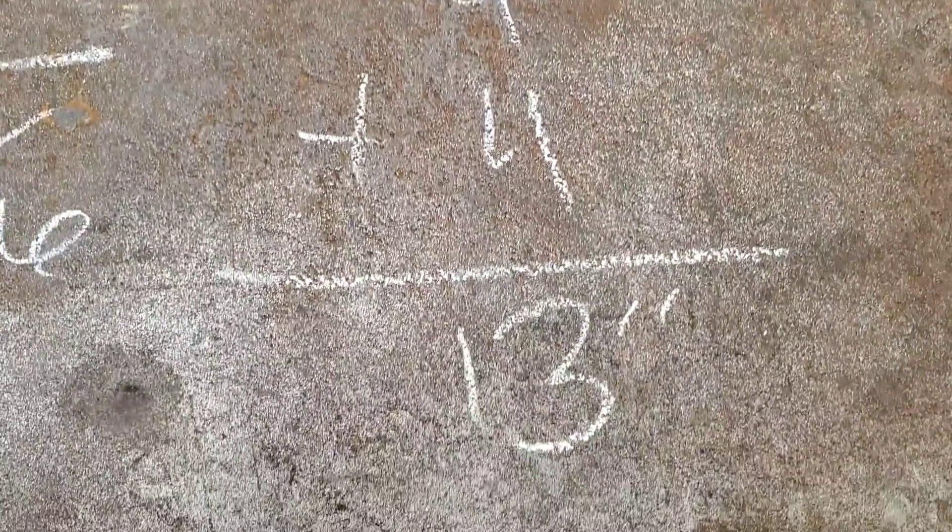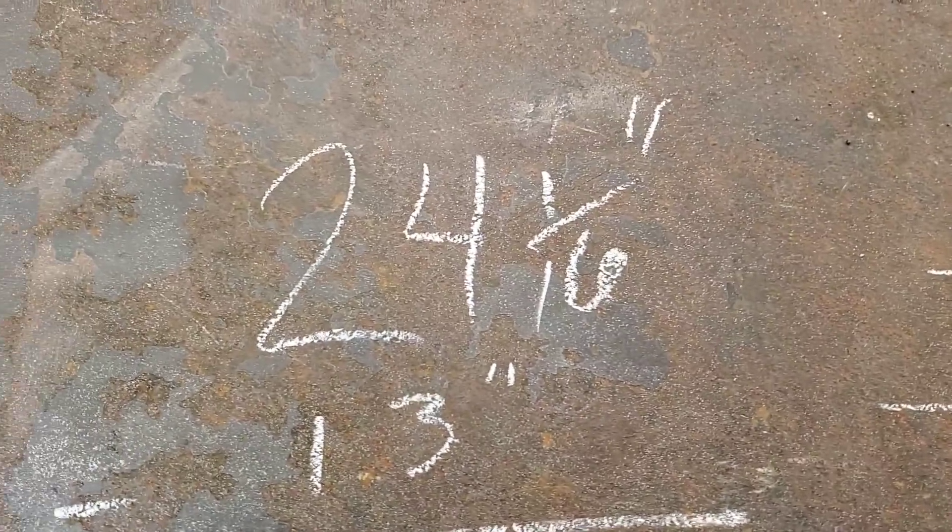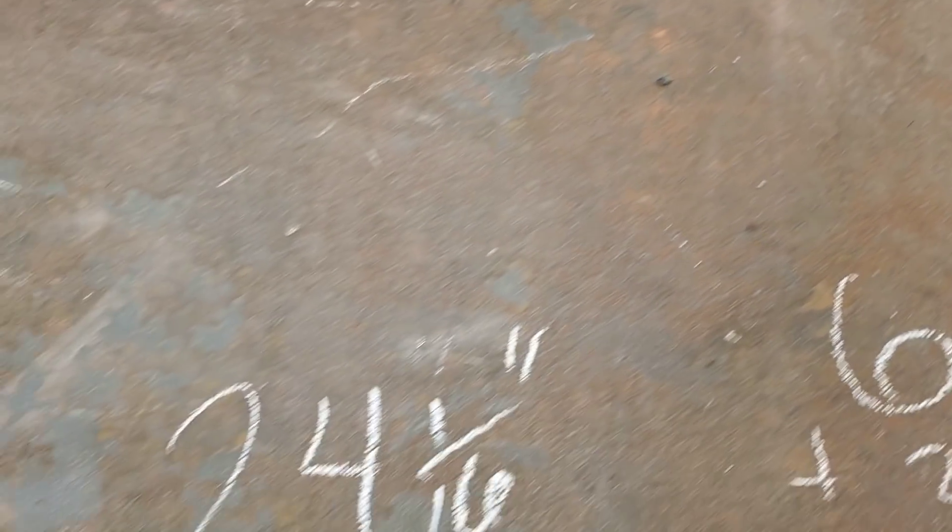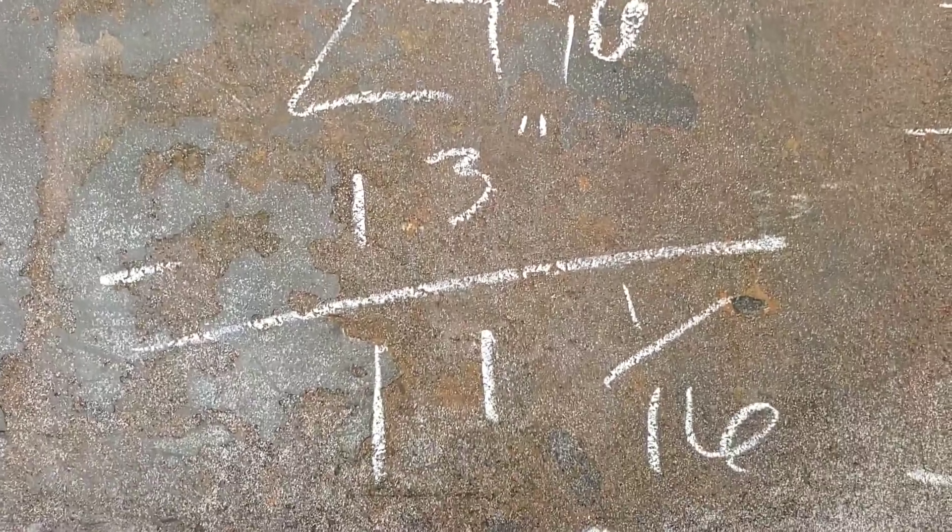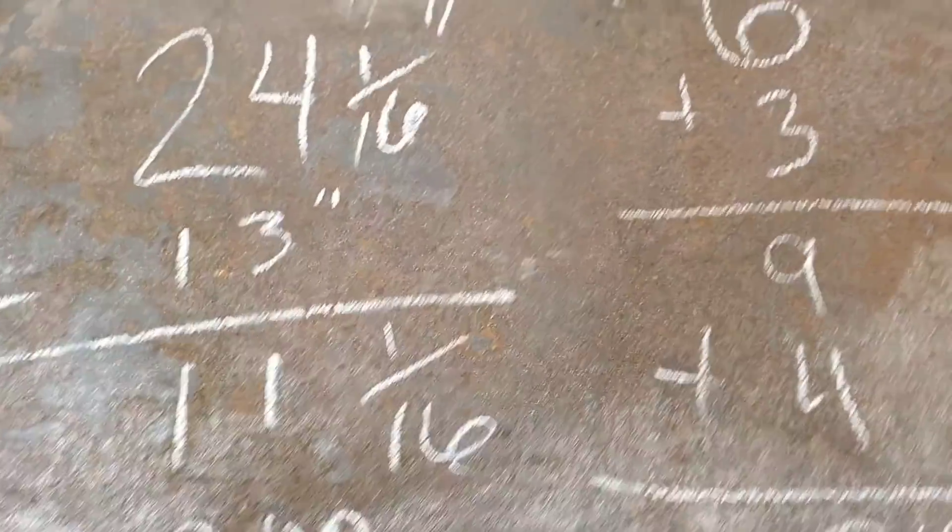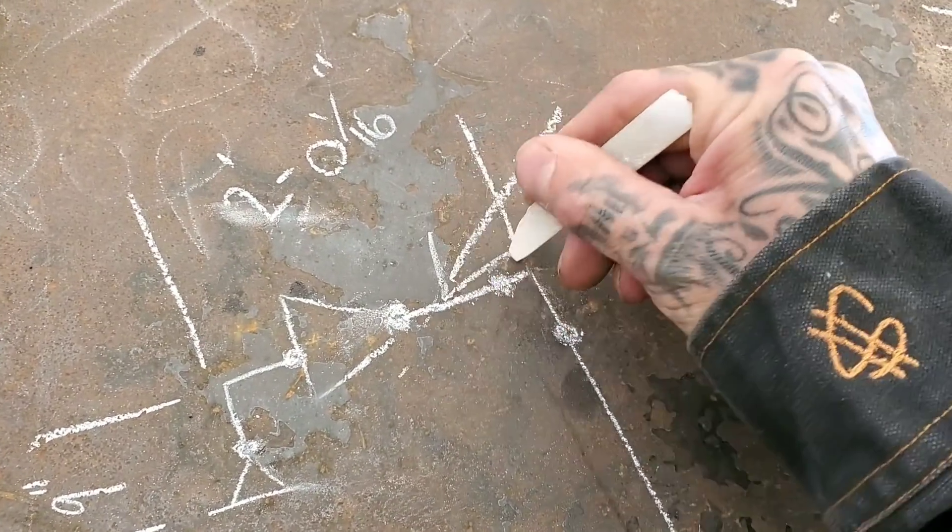Now we know that six plus three equals nine, plus four equals 13. This is my center to center in inches. I took two feet and made it 24 and a sixteenth, subtract 13, it's 11 and a sixteenth pup. Now that'll be the pup length in between my fittings.